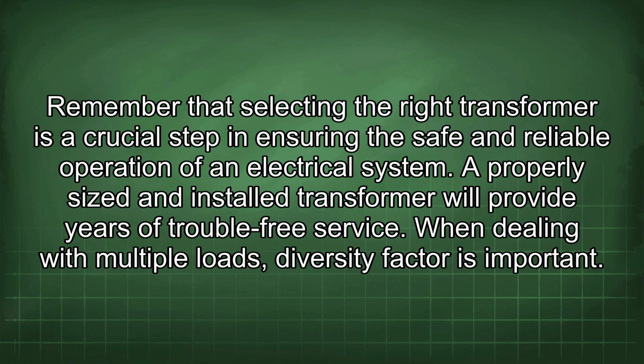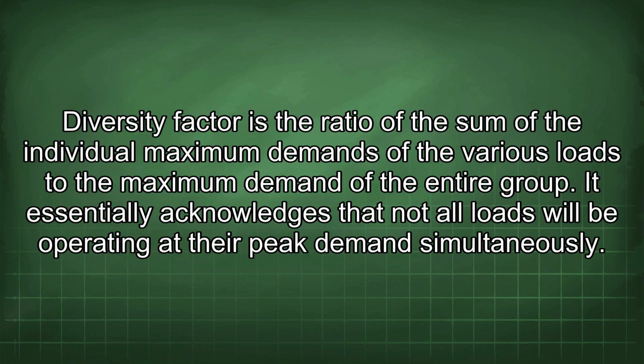When dealing with multiple loads, diversity factor is important. Diversity factor is the ratio of the sum of the individual maximum demands of the various loads to the maximum demand of the entire group. It essentially acknowledges that not all loads will be operating at their peak demand simultaneously.